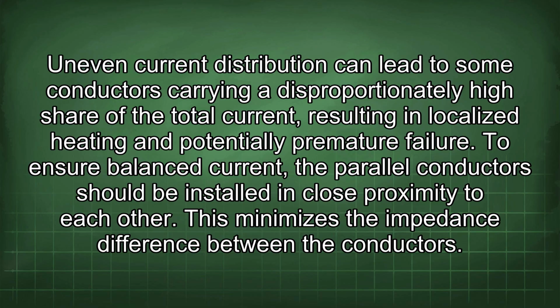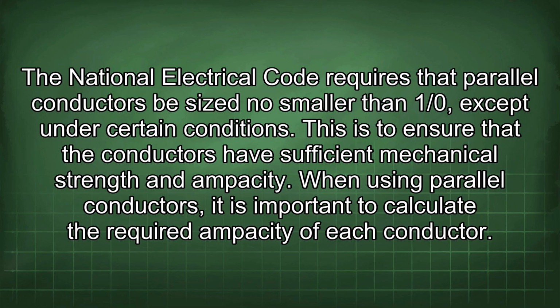To ensure balanced current, the parallel conductors should be installed in close proximity to each other. This minimizes the impedance difference between the conductors. The National Electrical Code requires that parallel conductors be sized no smaller than 1/0, except under certain conditions. This is to ensure that the conductors have sufficient mechanical strength and ampacity.